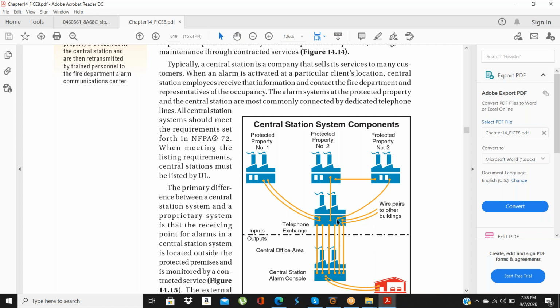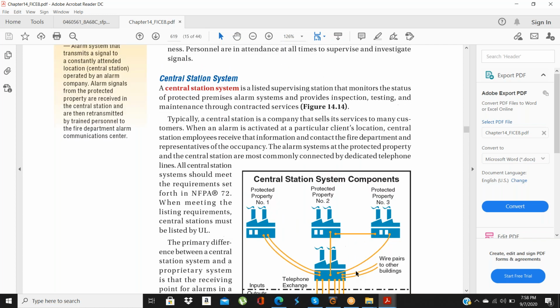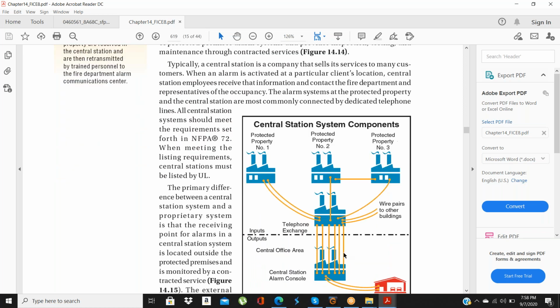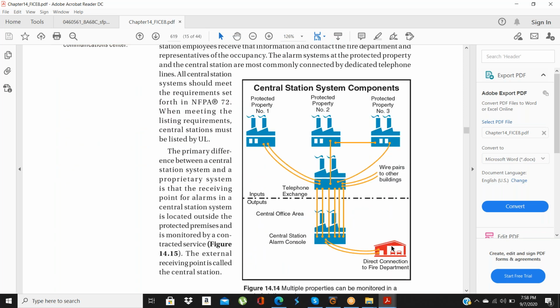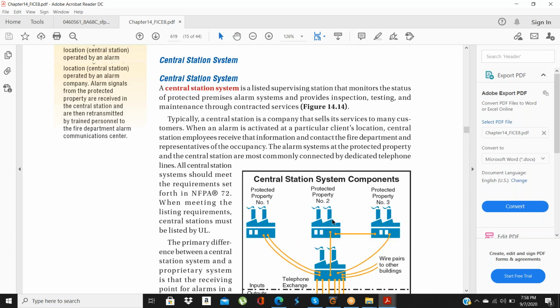In proprietary, there is no operator from a third party; the property owner sets his own person, who contacts the fire emergency department. In remote, this is all automatic. The signal goes directly to the municipality, because it may be connected automatically with the municipality, which goes directly to the fire emergency department, municipality, etc., who provides the service for fire extinguishing. Now it's clear, there are 4 systems.